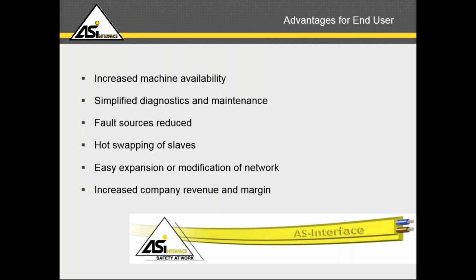Also, the end users have huge advantages, and the machine has higher availability due to simplified diagnostics and maintenance. Fault sources are reduced since wiring is very simple. As Glenn described to you earlier, wiring faults can occur, and you have a very hard time diagnosing that fault. Here, diagnosing a fault is very simple. At the same time, hot swap of the slave means the machine doesn't necessarily have to be out of commission for repair, because it's very simple to replace an ASI device compared to conventional devices.